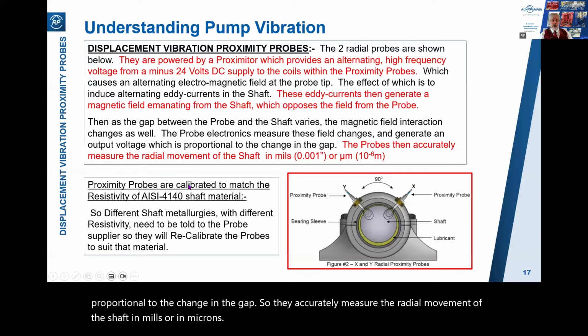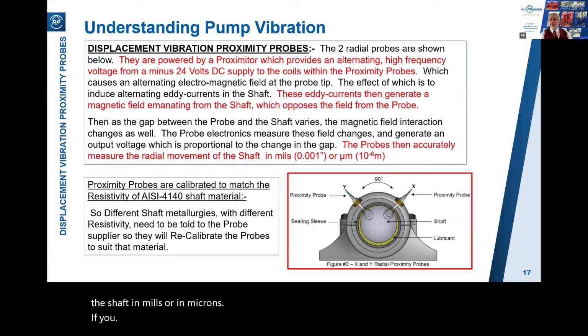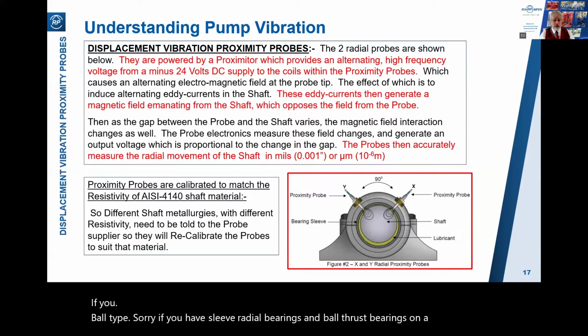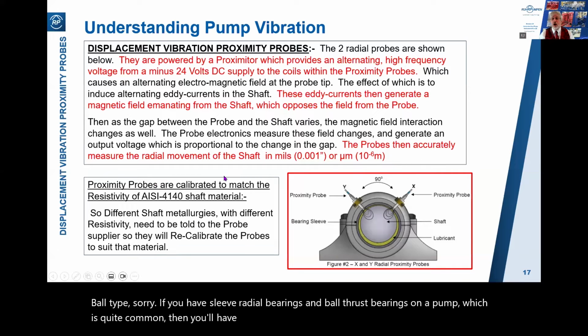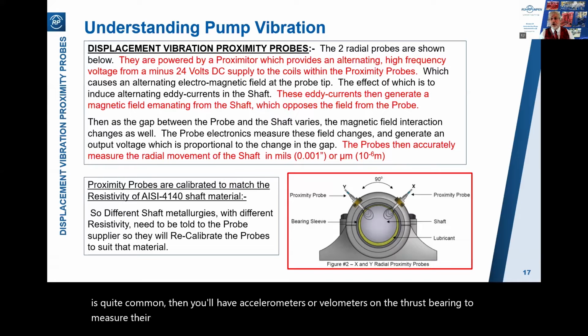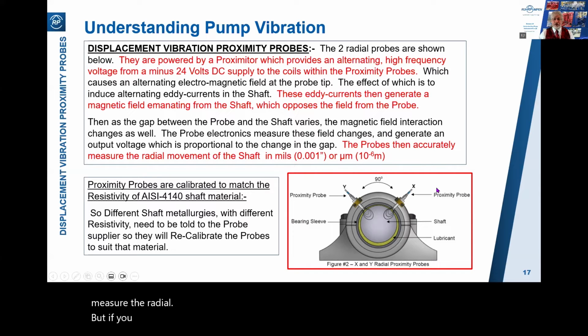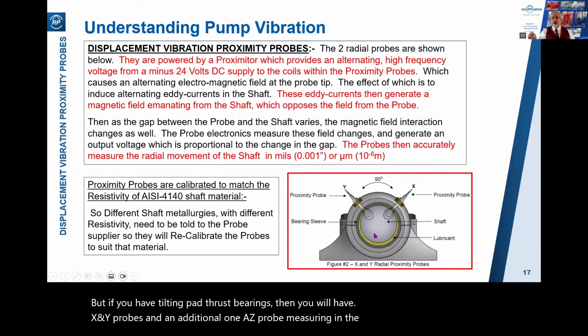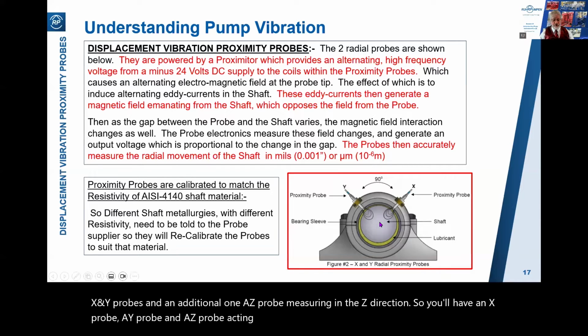If you have sleeve radial bearings and ball thrust bearings on a pump, which is quite common, then you'll have accelerometers or velometers on the thrust bearing to measure their vibration, and you'll have the proximity probes in the X and Y directions to measure the radial deflections. But if you have tilting pad thrust bearings, then you will have X and Y probes and an additional one, a Z probe, measuring in the Z direction. So you'll have an X probe, a Y probe, and a Z probe acting on the end of the shaft there.